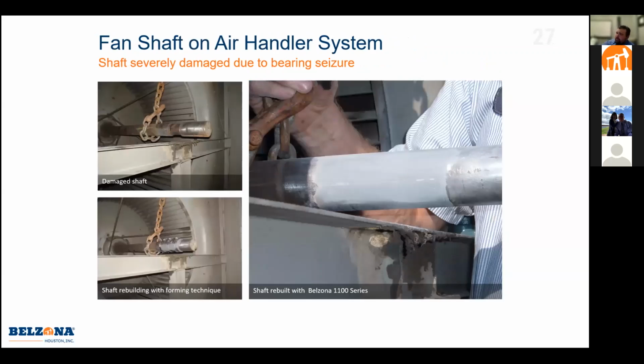Now this, having my machinist and millwright background, this is probably one of my favorite repairs. Let's say your air handler fan shaft bearing spins and fails, basically destroying your shaft in that area. Typically where your air handlers sit inside your building or units, it's very hard to get in there to replace or take anything apart. So we have a solution using clamps and formers specially machined for your shaft OD, and we use a Belzona paste grade to reform that and get you back up and running in about a day's time. The formers we can make through a machine shop that partners with us, typically in 2 to 3 days.